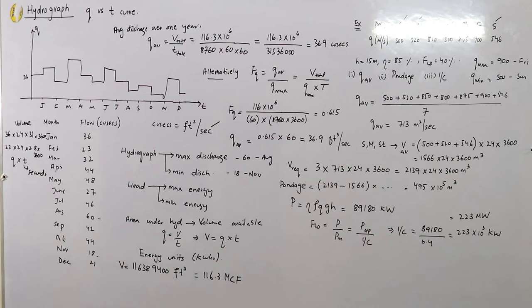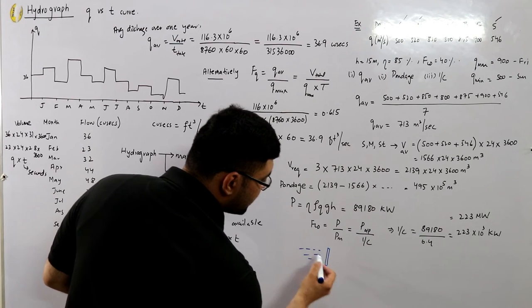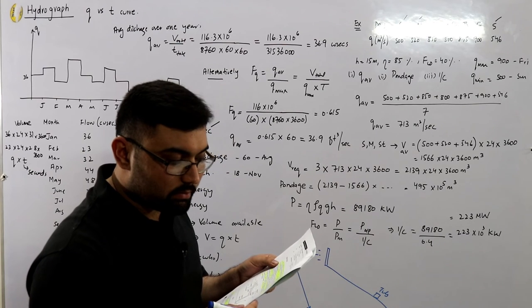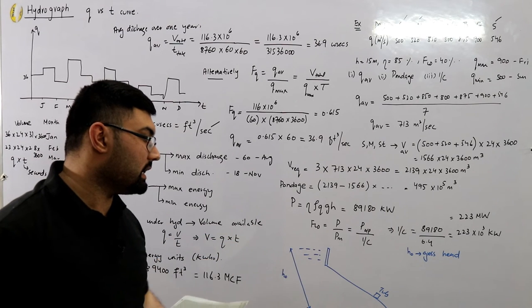The effective head is the head from the center of the intake to the center of the turbine. Looking at the diagram: the dam has a maximum reservoir level; water flows down through the penstock to the turbine, and the tail race represents the minimum level. The gross head H₀ is the vertical distance between the maximum water level in the reservoir and the tail race.